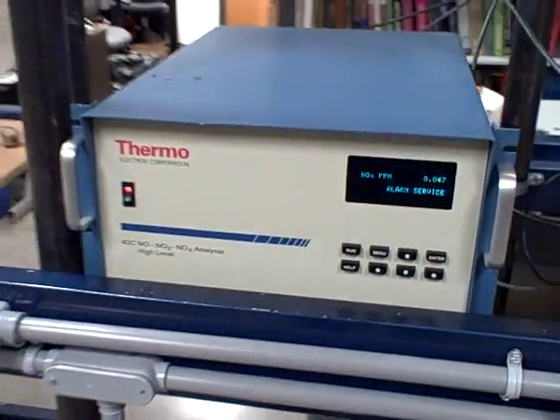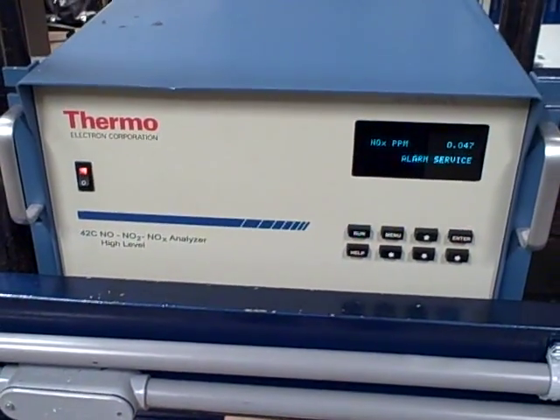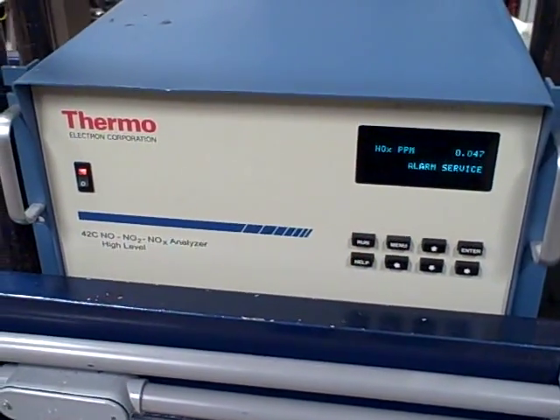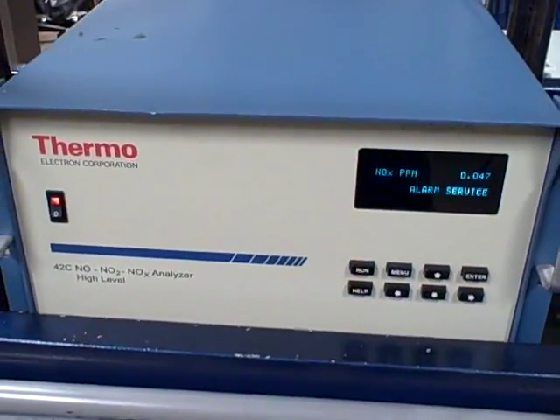Over here we have a Thermo Electron Corporation NOx analyzer. It also uses chemiluminescent technology like the Rosemount 951C — generating ozone with instrument air, letting the ozone react with the nitric oxide gas, and that produces a small amount of light which is measured by a photomultiplier tube.